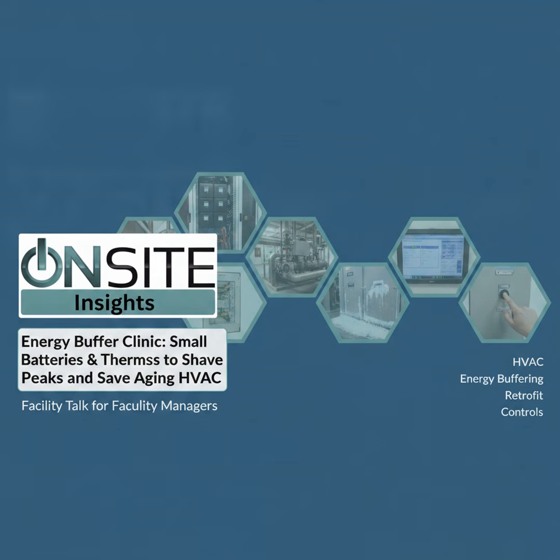Simple rules of thumb. If you're protecting control electronics and preventing nuisance trips, size for 300 seconds of hold. For demand charge shaving or scheduled load shifting, you need hours. Cost-wise, targeted pilots, think 2K to 10K, are common and can be justified by avoiding a single emergency replacement or a few service calls. Factor in possible utility rebates too.